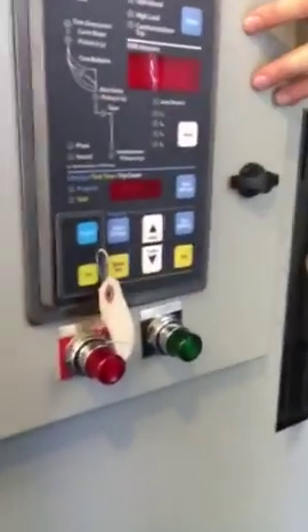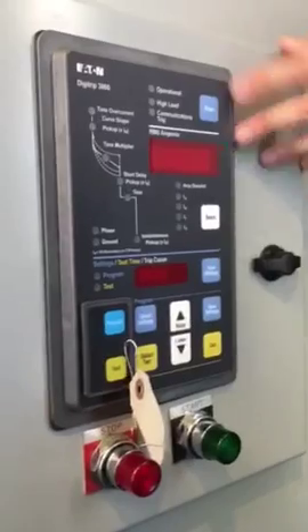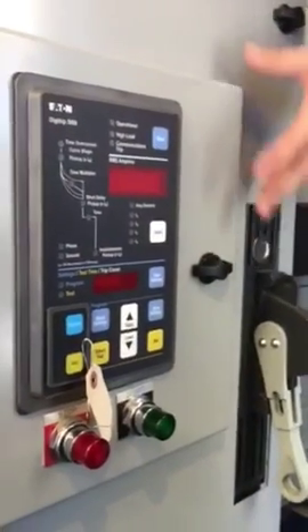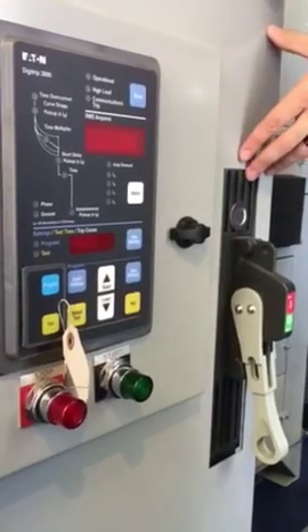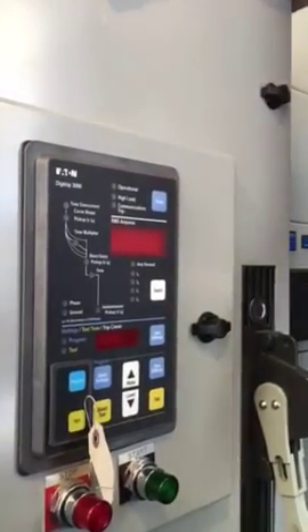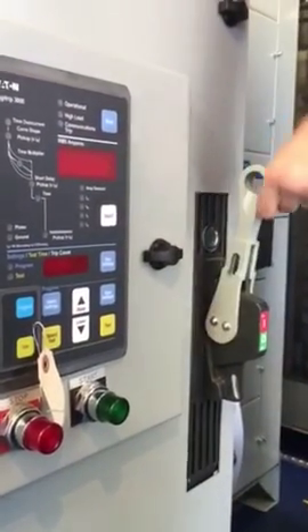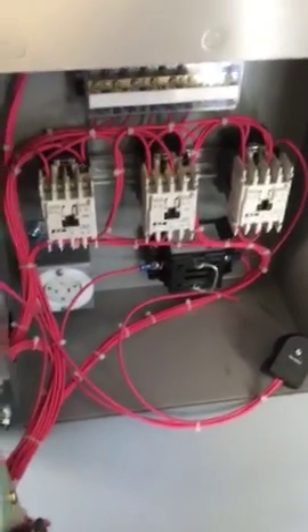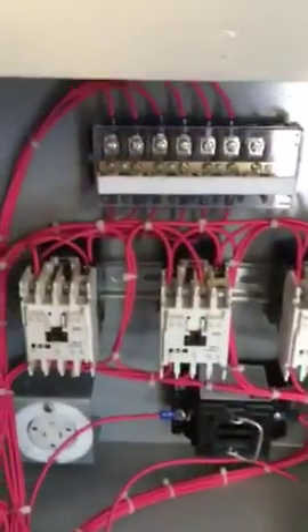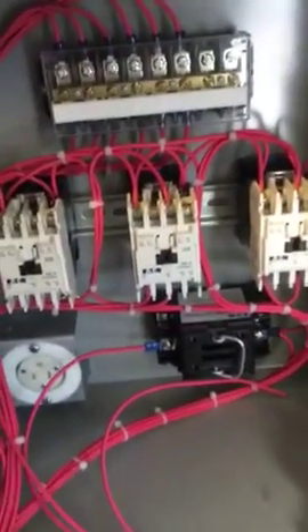And then probably the most important feature of this is that all of your controls for the device as well as your protection are on the front panel in its own separate compartment. Whereas the older style AMPGARDs, you actually have a slide out drawer and you have to de-energize your motor, open your isolation switch. This door can be opened with the isolation switch closed with the motor on, and you can do all your troubleshooting with the motor actually on and verify that the system is either operating with your PLC, with your SCADA, building automation, whatever you need to do on a 120 volt or 24 volt DC, you have access to without being exposed to the 5 or 15 kV high voltage.